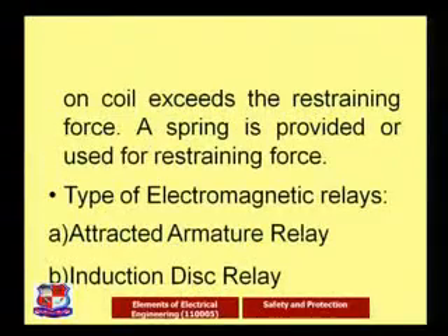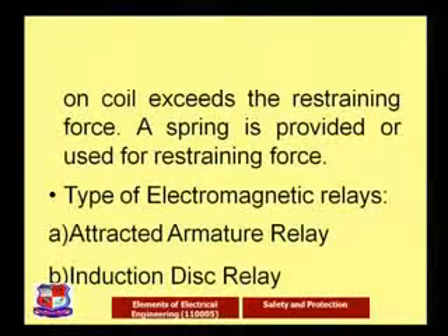But when normal conditions are there, what happens? The restraining springs, or the restraining forces, bring the contacts back to the normal condition. So that is the major difference between the operating force and the restraining force. If the operating force becomes greater than the restraining force, it indicates there is going to be a fault condition. The trip coil is going to give the tripping signal with the help of the sensing of the relay in that case. A spring is provided, which is used for the restraining force.